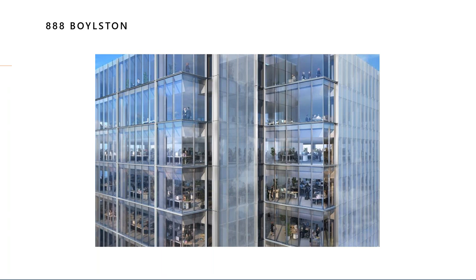One of the things to be very aware of when you're designing a system with chilled beams is that it has a limitation from a load per square foot perspective. So if you have a space that has super high solar heat gain, which quite frankly with the energy codes now, it's going to be harder and harder to have a space like that. But you have to pay attention to the glazing performance. Even though this building performs really well, we did post occupancy measurements on it for a year, and it was performing even better than the 44 EUI that had been predicted. I think it was more around the 40 or 41 range, fully occupied.